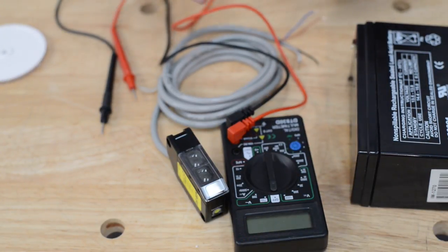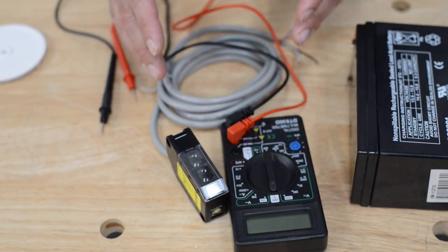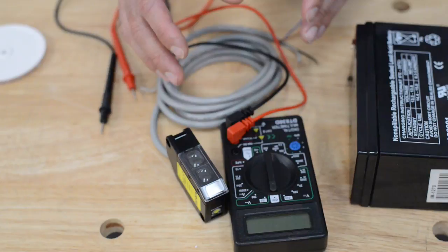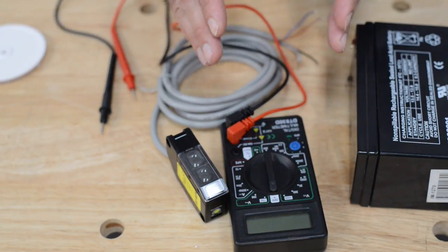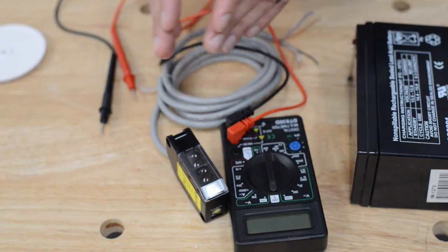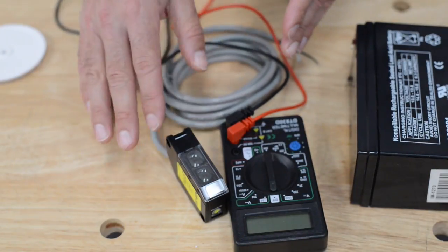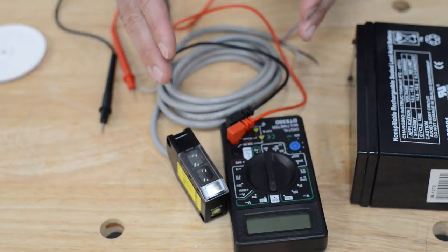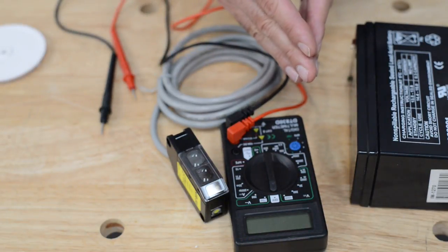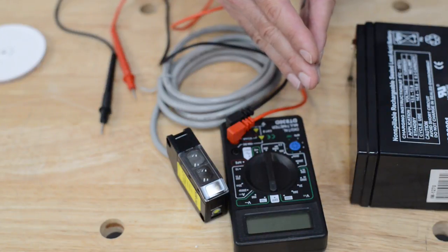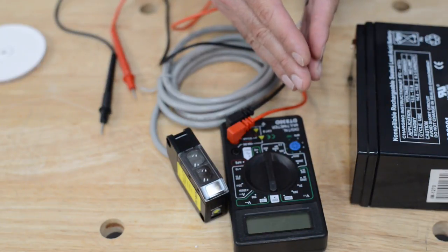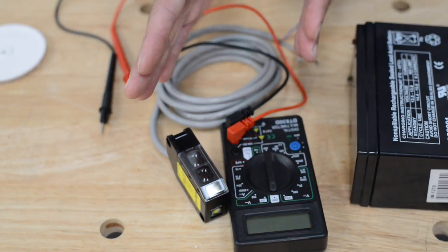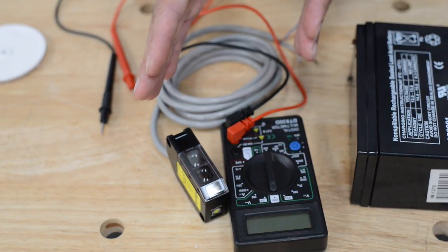Just a quick explanation. What a relay is, is when it gets applied power to the coil side of the relay, an action happens where the common moves from normally closed to normally open. So in the normal state of a PhotoEye, when the beam is connected, the normally closed would be connected to the common and then when the beam is tripped, the paddle inside, the metal paddle that's making this connection, flops over to the normally open, closing that circuit.